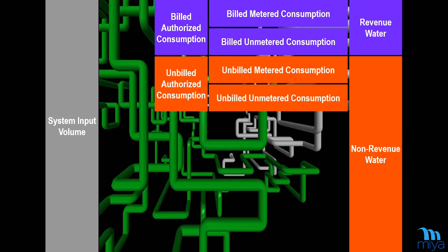Revenue water could be either billed metered consumption or unmetered consumption — all of this is billed authorized consumption. But then we also have unbilled consumption, which is also authorized, and this consumption can be either metered or unmetered. The trouble is this unbilled authorized consumption is already part of non-revenue water. People are allowed to use this water but we don't get revenues for it. A good example for unbilled unmetered consumption is, for example, firefighting. What if mosques get water for free? This can be either metered or unmetered, but definitely it is authorized consumption and part of my non-revenue water.